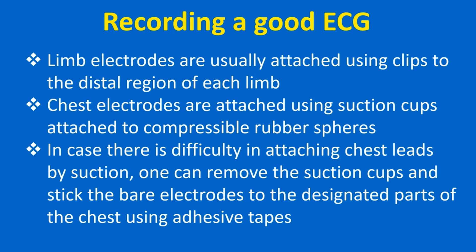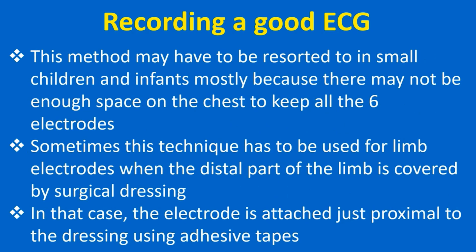In case there is difficulty attaching chest leads by suction, one can remove the suction cups and stick the bare electrodes to the designated parts of the chest using adhesive tapes. This method may have to be used in small children and infants, mostly because there may not be enough space on the chest to keep all six electrodes. Sometimes this technique also has to be used for limb electrodes when the distal part of the limb is covered by surgical dressing — in that case, the electrode is attached just proximal to the dressing using adhesive tapes.